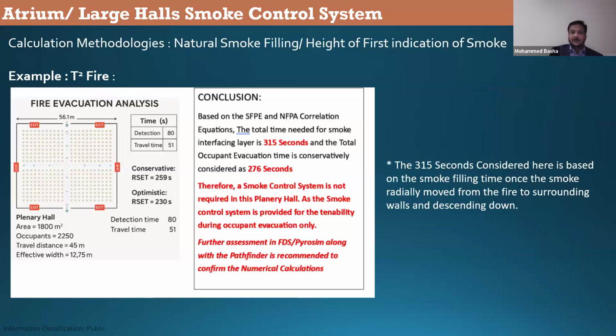So as long as the buoyancy is there, it will go up. Smoke will have a lot of buoyancy because of the heat energy created by the fire. It will go to the top of the ceiling, hit, and come down. So it needs some time for the travel. That's why this 315 seconds is considered. This is also not my numbers. This is based on the Society of Fire Protection Engineers book calculations.